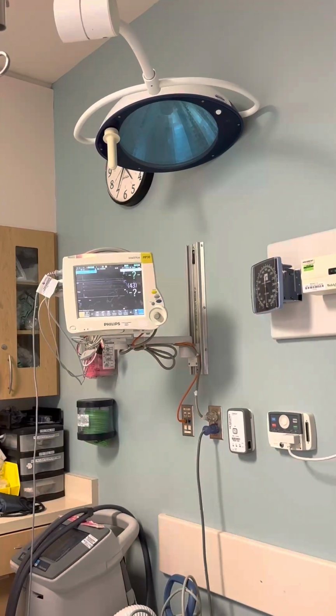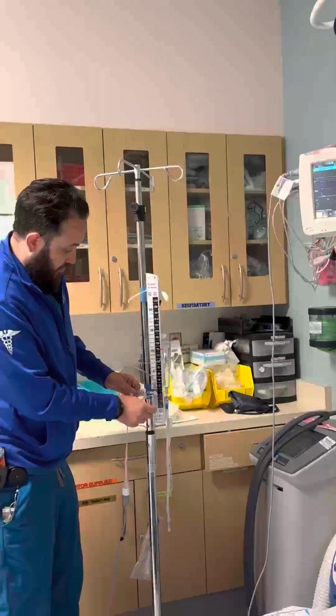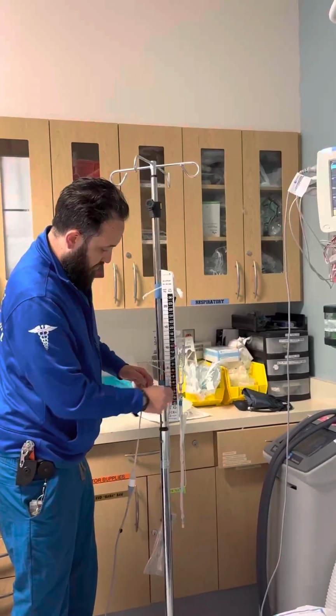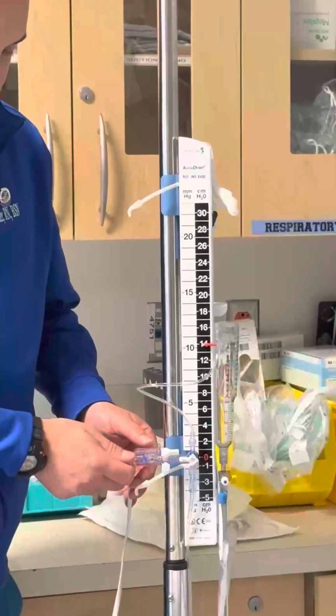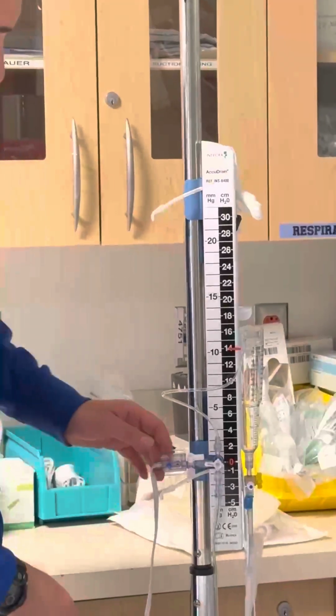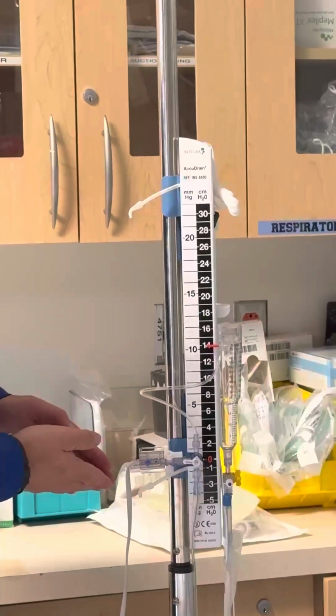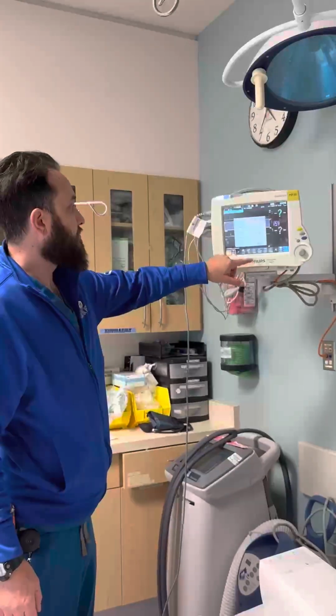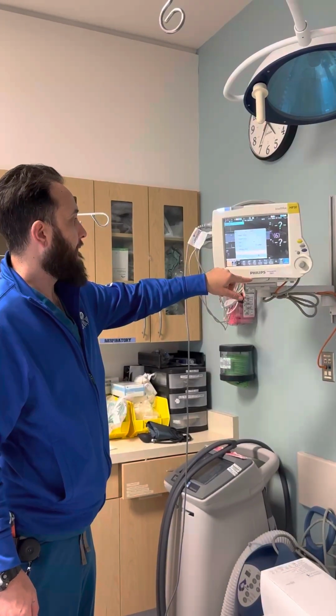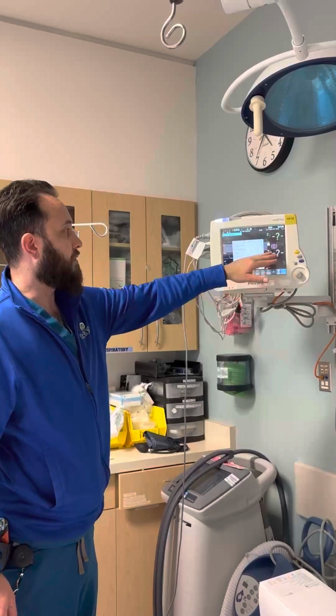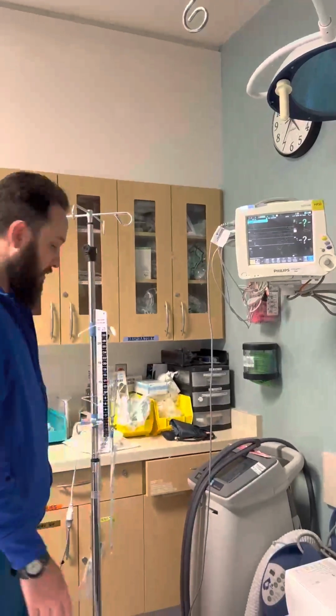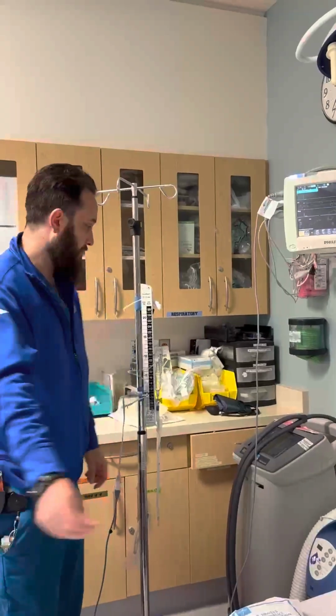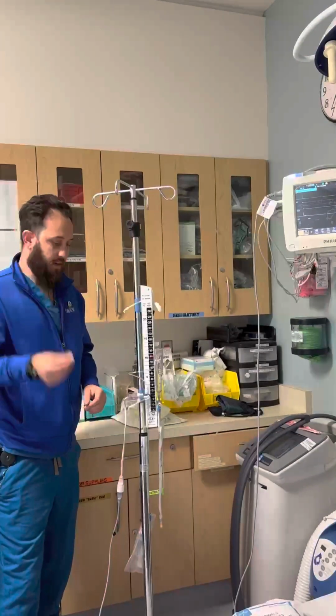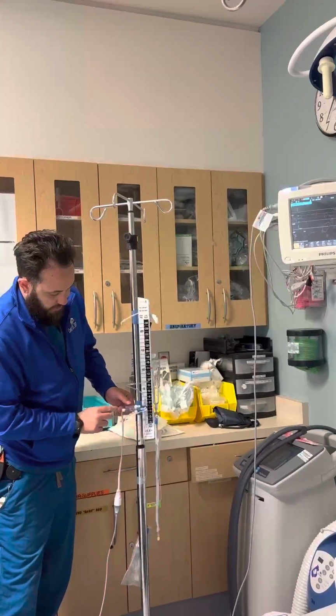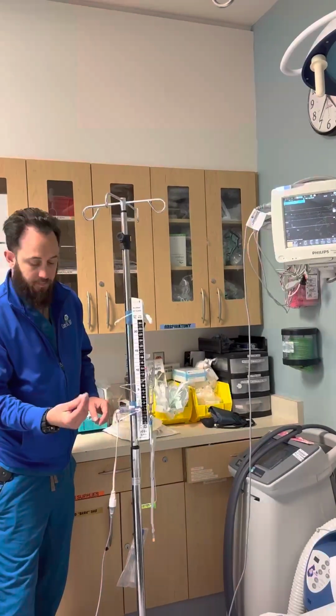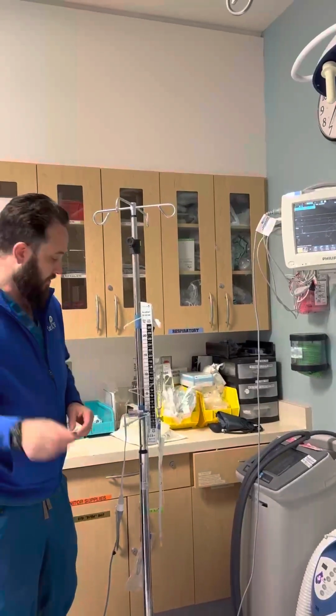To zero it, you want to turn it off to the patient. Open this clear cap. You have it now open to atmospheric pressure to the transducer. You click on the line, zero ICP, and then it's going to count down, and then you'll have a 0. That means you are now zeroed. You want to get the cap. Inside the transducer kit, it'll have a white cap that you just replace it with, and it should have 2 because you want to change this white cap and this other clear cap to the white cap, because these caps have a little hole in the center.